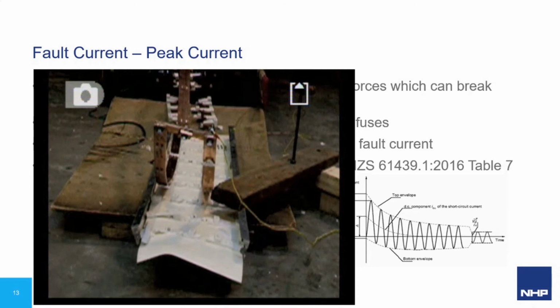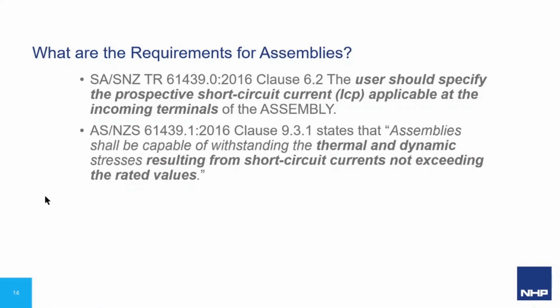Again, the peak current available can significantly be reduced by implementing moulded case circuit breakers or fuses, which will operate under a short circuit condition to reduce the peak. The last requirement of our assembly is to consider if we have appropriate upstream protection devices.